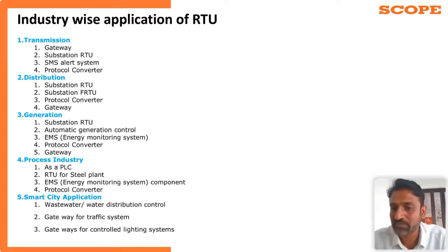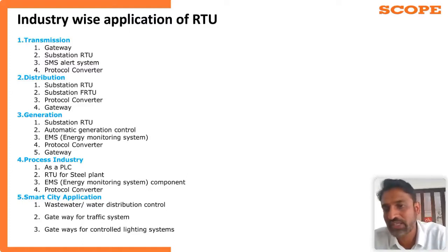But when you are constructing a new substation, definitely we will go for the latest BCUs, RTUs and relays. This particular solution is mainly for old relays, old substations, which will be converted into the automation system without changing the existing relays and existing cablings. This will be helpful and very economical also.